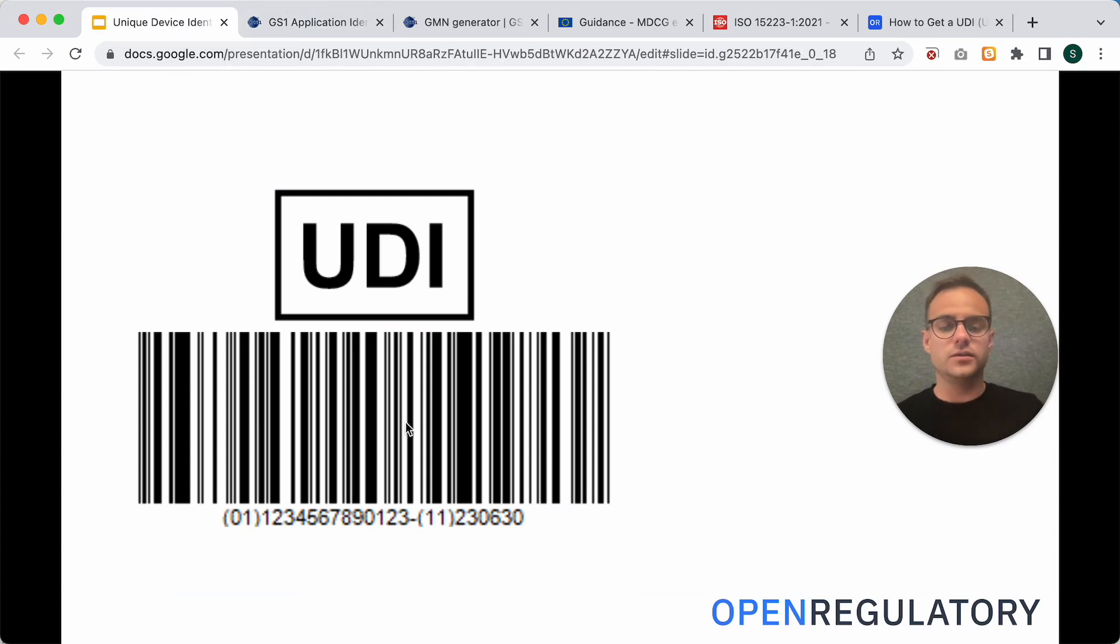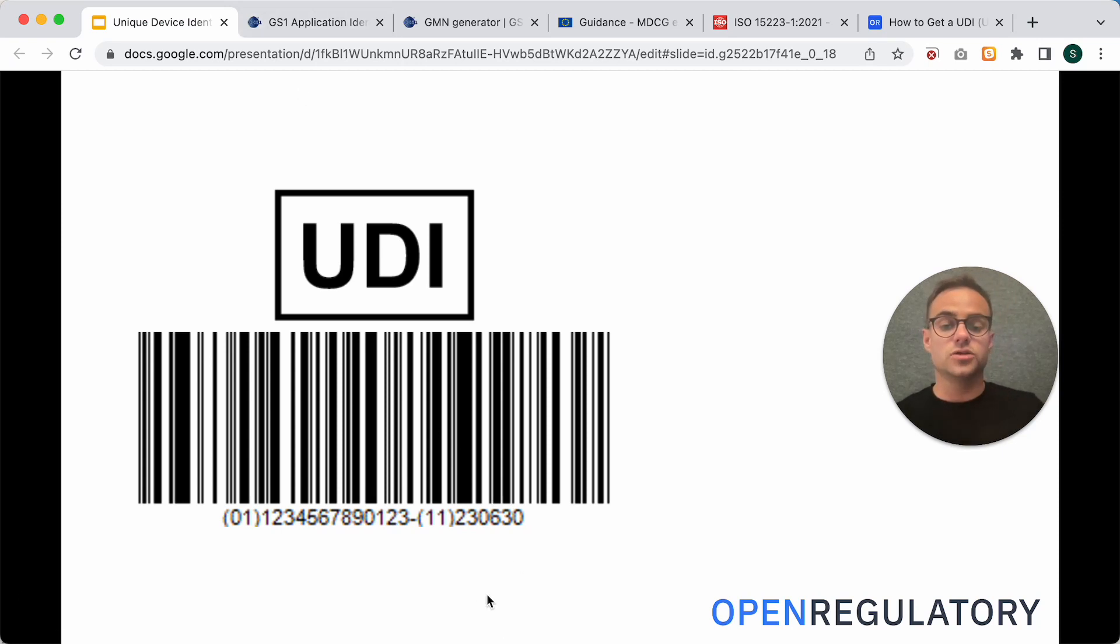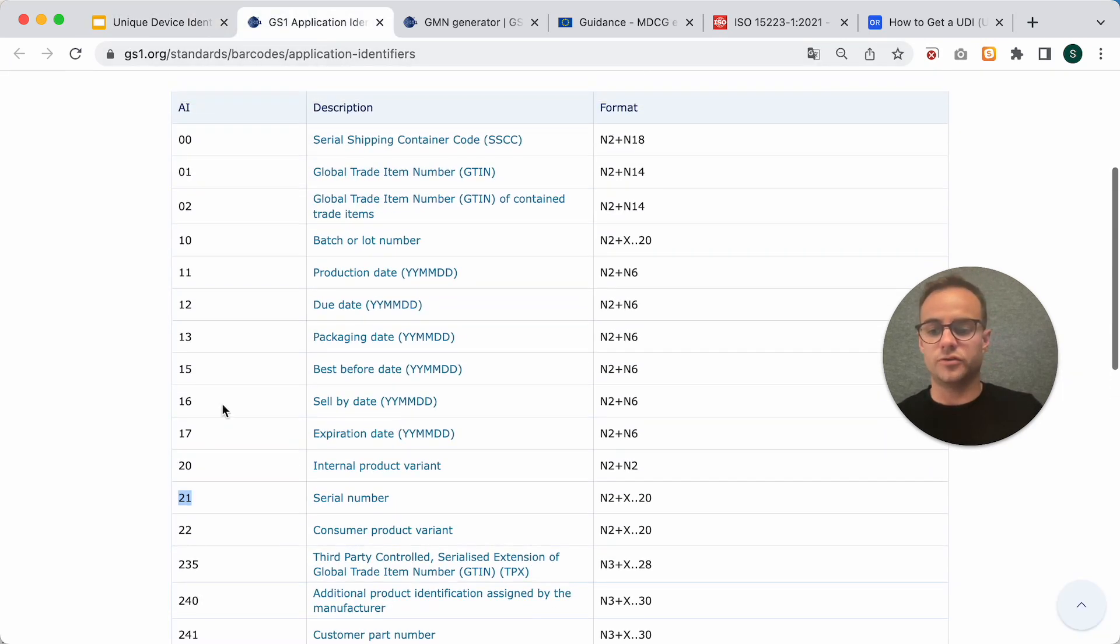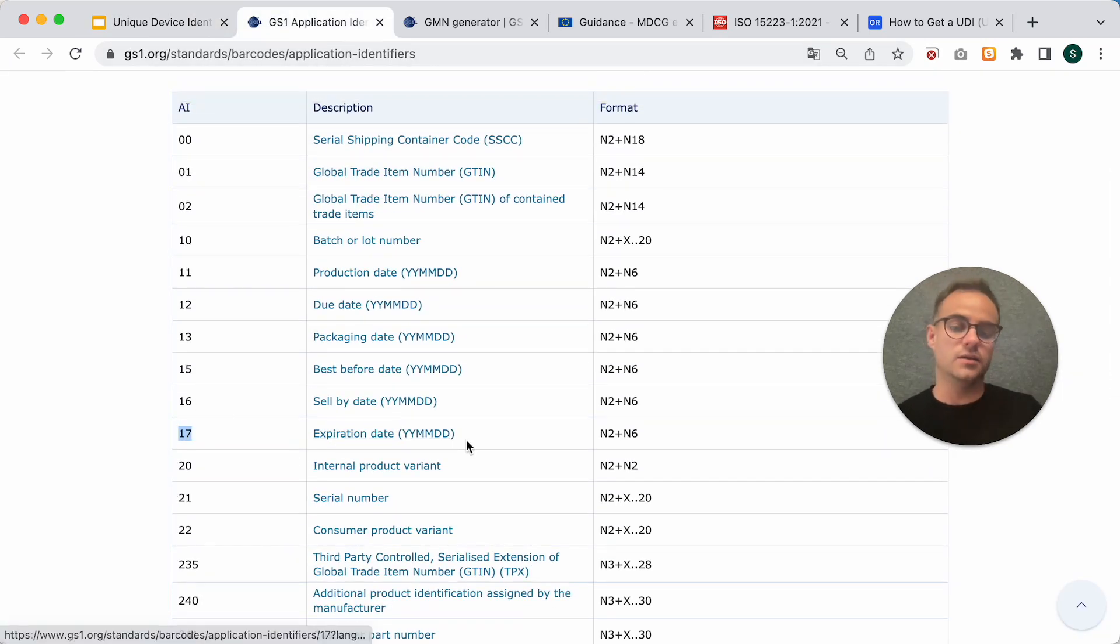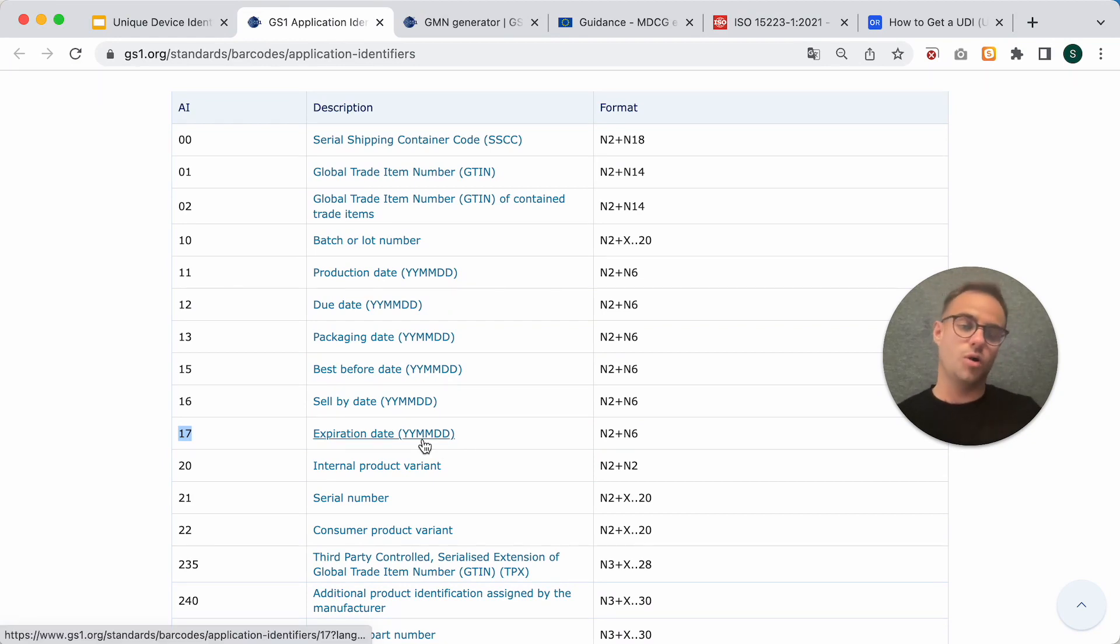And the UDI-PI can actually be multiple things. It doesn't only have to be one. So, you could, after this 11, you could also add, for example, a 17 and then add an expiration date for the device. That's all possible.